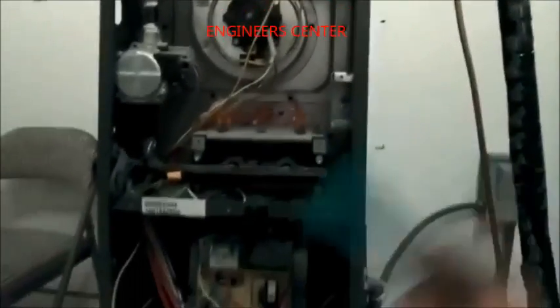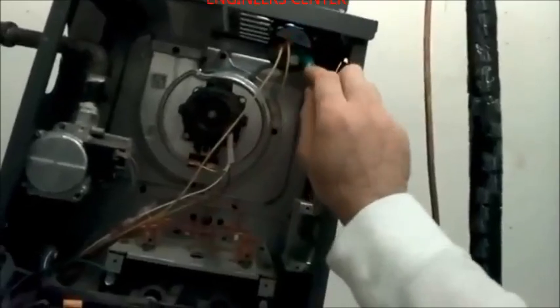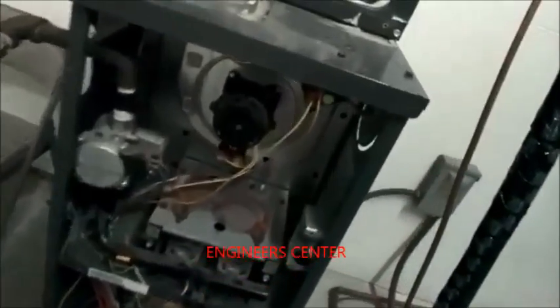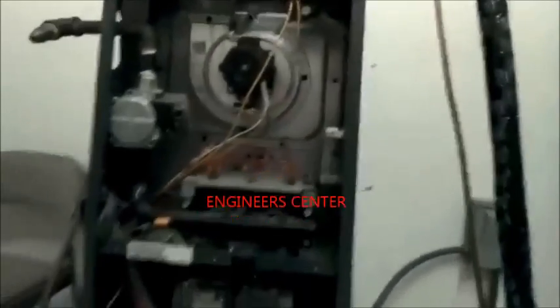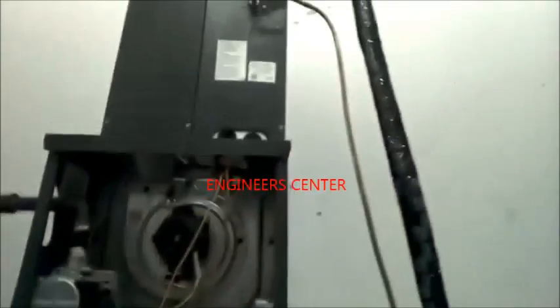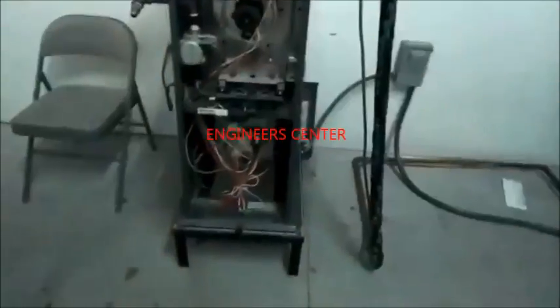So you have to know a sequence of operation and what parts do. If I didn't know that this pressure switch closed off a pressure, how could I diagnose it? If I didn't know that that came on first and this closes second, we spark or glow third, I wouldn't be able to fix it. So, and then also once it does ignite, let's say it ignites and everything's good. We're heating. Why are we here? It's heating just fine. Well, maybe there's going to be a safety or a limit that goes off. And so if the heat turns off for a second, you go through with your meter now looking for voltage, looking at this limit here. Find the limit that opened. Why did the heat go off? And if a limit opened, then you have to wonder, did the limit open because it was supposed to? Or did it open because it was doing its job, and maybe the coil's dirty, and there's no airflow, therefore the limit did open for a reason. So you just got to know your sequence of operation, and you can fix it. Hope that helps.